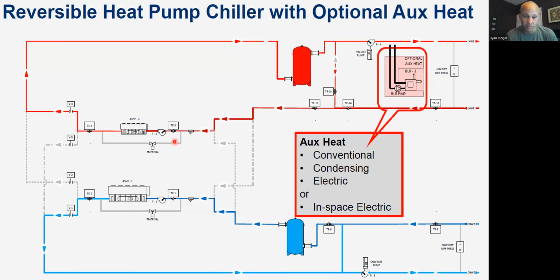This one is one that has a reversing valve on the refrigerant side. So I apologize. There is a reversing valve on the refrigerant side. In this case, there are 2 air-cooled chillers on here. There's a bigger one and a smaller one in this particular case. So this one's making chilled water, doing his thing over here. This one is making hot water in this example, and there's piping between the 2 of them. That's the gray dotted lines.